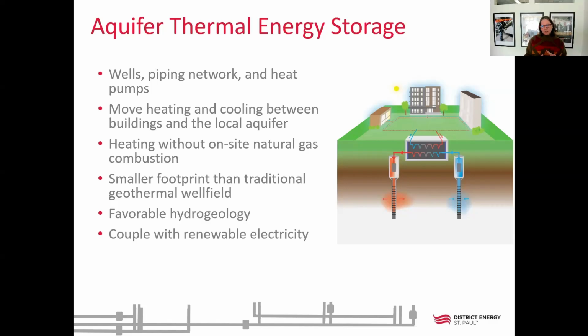The way that this works is the aquifer itself is between 50 and 60 degrees, and we just take that aquifer water and run it through a heat exchanger, so that we're taking that 50 or 60 degrees and transferring it to the district system. Then they use a heat pump to bump that temperature up to 120 or 140 degrees, what they need in the buildings, or to bump it down to 42 degrees for cooling. So this is electrifying building heating, but it's not 100% electricity, which can be cost prohibitive. Using this aquifer gets you to that 50 to 60 degrees, and you just need the electricity for that additional bump up for heating, or bump down for cooling.